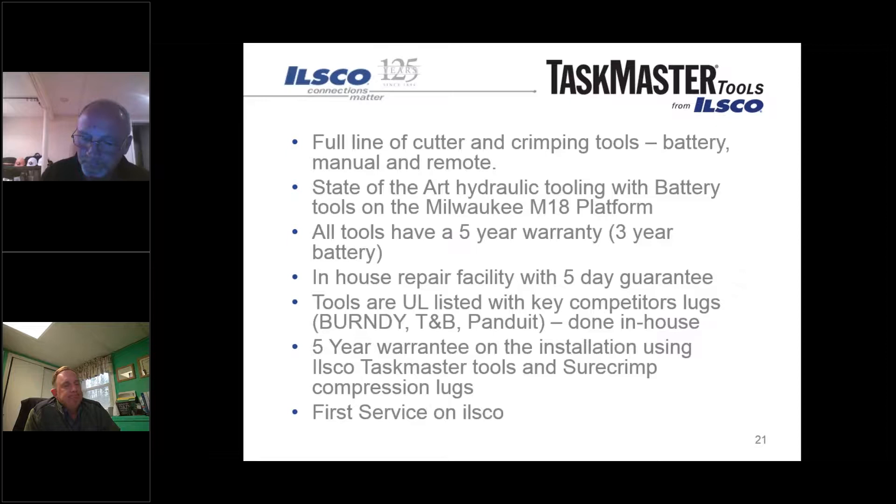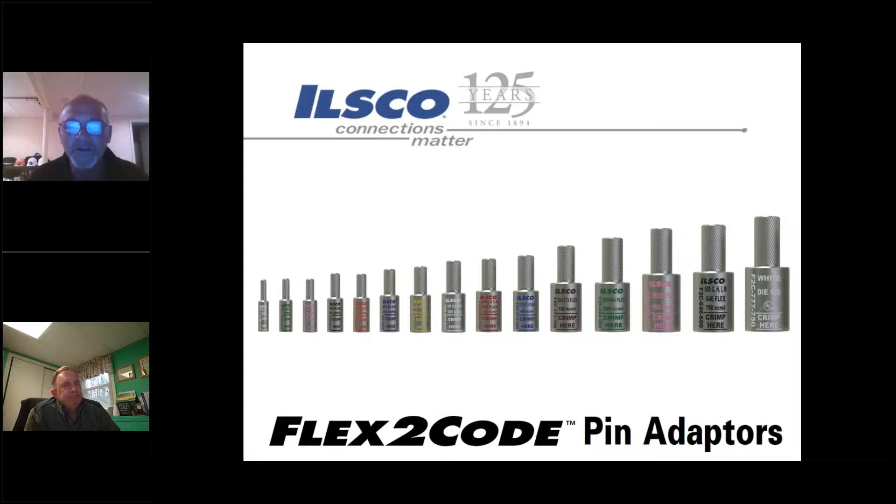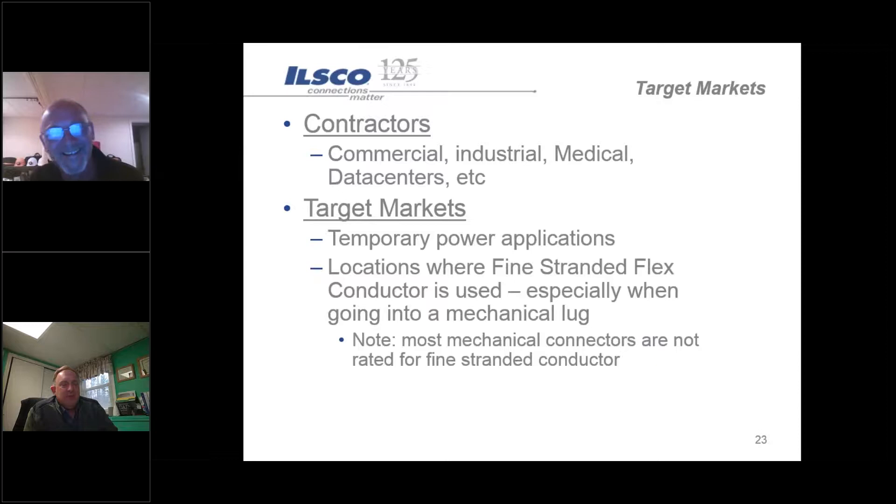ILSCO has just redesigned all their pin adapters. Now moving on to the Flex2Code pin adapters - their primary use is for applications where customers are going from a fine strand conductor, whether it's DLO, Class G, H, or K - any fine strand or extra fine strand conductors - which typically require a pin terminal. This can be used in commercial, industrial, medical, and data center markets. A big use is for temporary power applications and anywhere fine strand conductor is used.